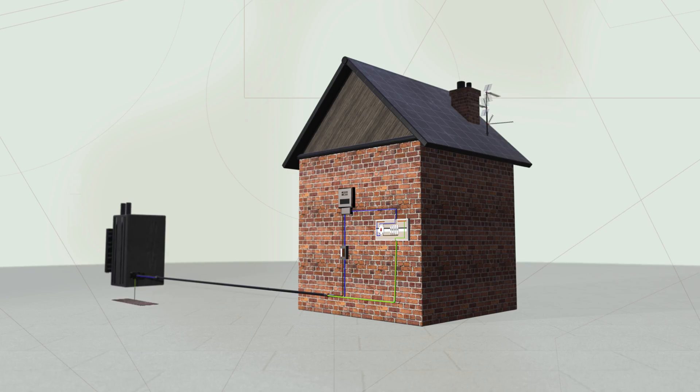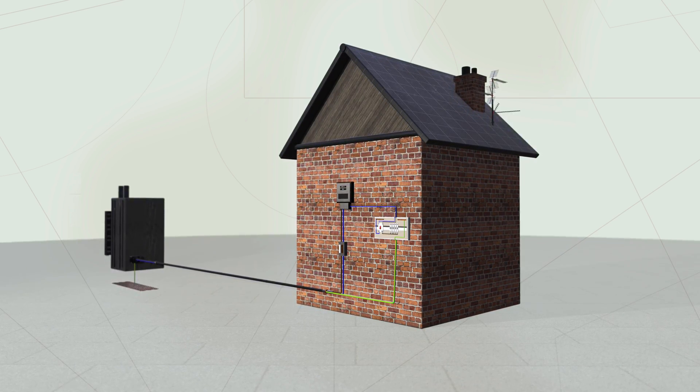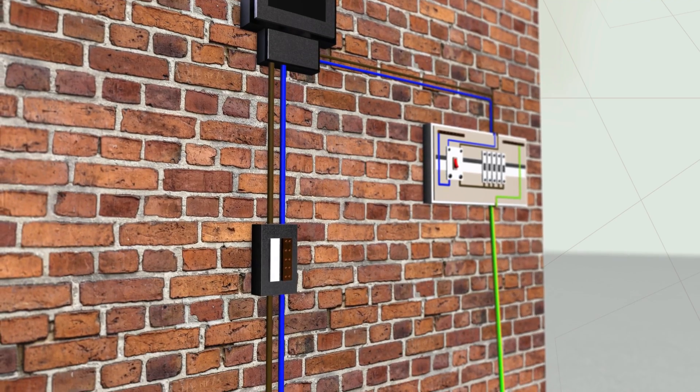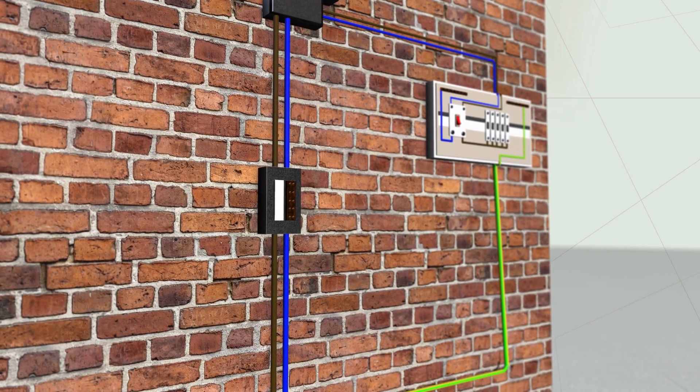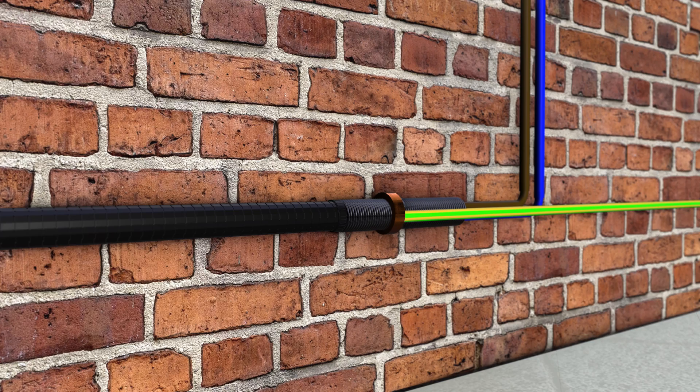Let's start with TNS. TNS stands for Terra Neutral Separate. From the distribution transformer all the way to the consumer's installation, the neutral and the earth are separate conductors. In a TNS arrangement, the earth and neutral are separate conductors from the distribution transformer up to the consumer's installation. The supply earth is normally the metallic sheath or armour of the supply cable.